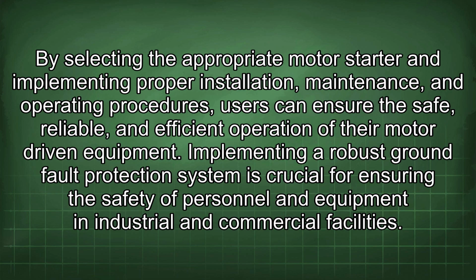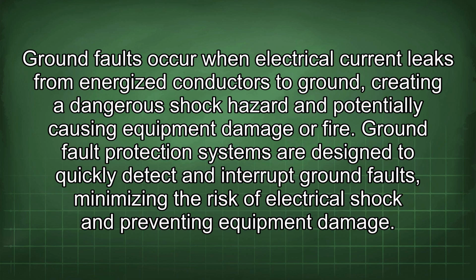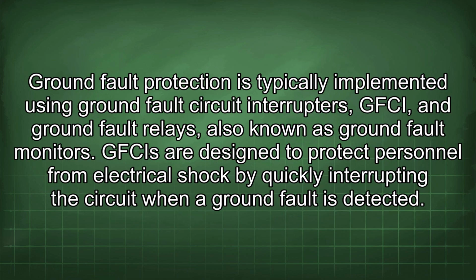Implementing a robust ground fault protection system is crucial for ensuring the safety of personnel and equipment in industrial and commercial facilities. Ground faults occur when electrical current leaks from energized conductors to ground, creating a dangerous shock hazard and potentially causing equipment damage or fire. Ground fault protection systems are designed to quickly detect and interrupt ground faults, minimizing the risk of electrical shock and preventing equipment damage. Ground fault protection is typically implemented using ground fault circuit interrupters, GFCI, and ground fault relays, also known as ground fault monitors.